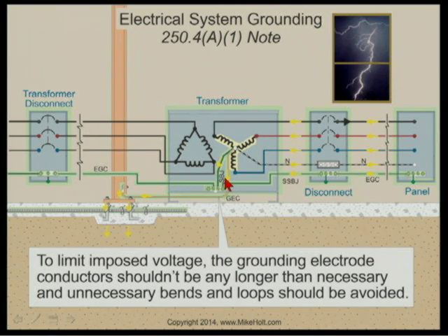You probably would be better off running 6-gauge wire from a 2,000 amp service to 2 ground rods than you would be running 500 kcmil or 3/0 or 4/0 or whatever it is, 50 feet or 100 feet over to some special ground bed. You've got to realize we're talking about high frequency discharging of energy, a little low frequency because you have static electricity, what have you. So people are thinking about the grounding electrode as somehow it's carrying a fault.